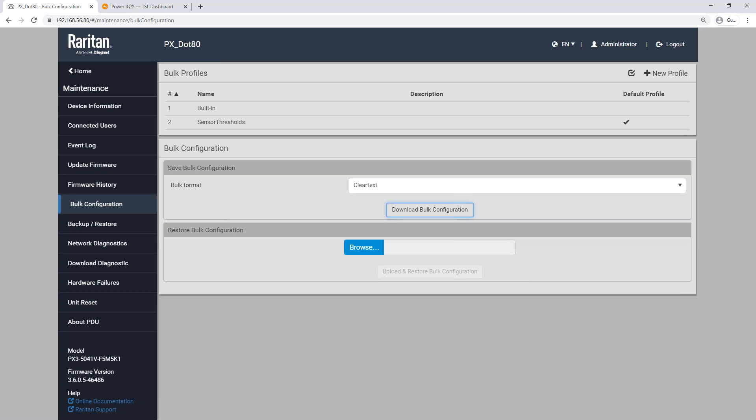There's another question: does the sequence of configuration steps for thresholds and alert config matter? Should event rule alerts be configured before thresholds are configured? Yes, event rules should be configured first. The reason is if you configure your thresholds first and they go into a warning or critical state, and then you configure your alerting — either SNMP or SMTP — because it's already in that warning or critical state, it's technically not going to become asserted and trigger that alert. So it is best practice to configure your event rules and notifications first, then set up your thresholds so that if you cross a threshold you get the alert immediately.